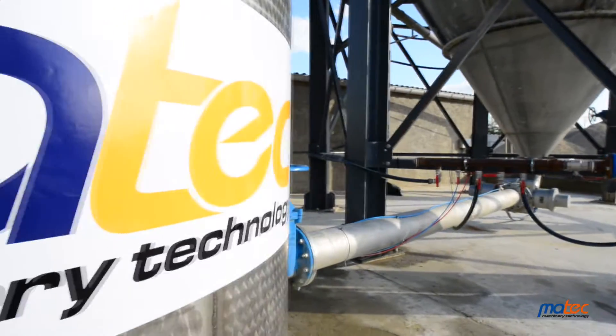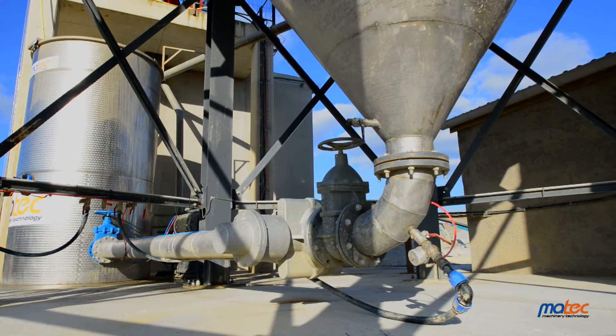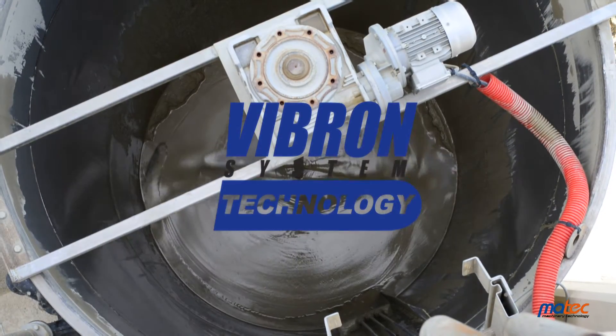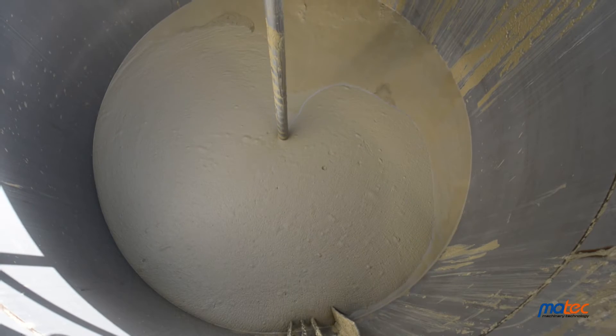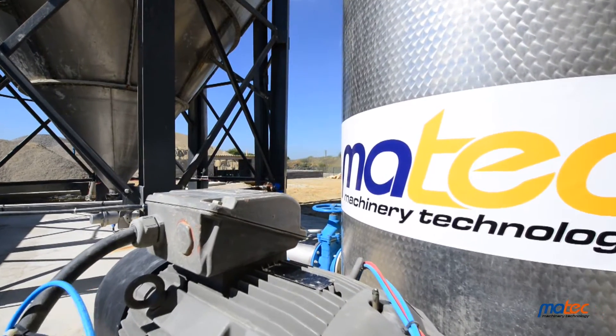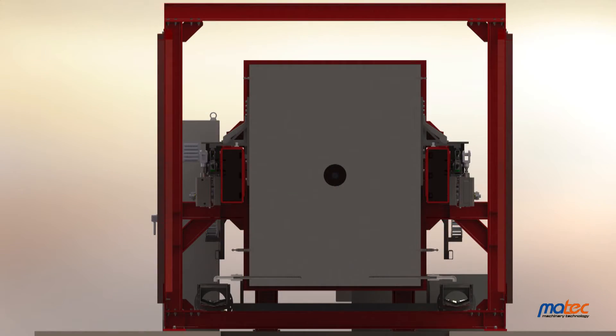Once it reaches the necessary compactness, the settled slurry is discharged by automatic valves and falls into the homogenizer tank. Thanks to the Vibron system, valves open only when the slurry has the desired density of 40-50% by volume. That is possible thanks to specific components like oleodynamic control units and pistons, oversized frames and high pressure pumps, and especially thanks to MATEC engineers' specialised design.